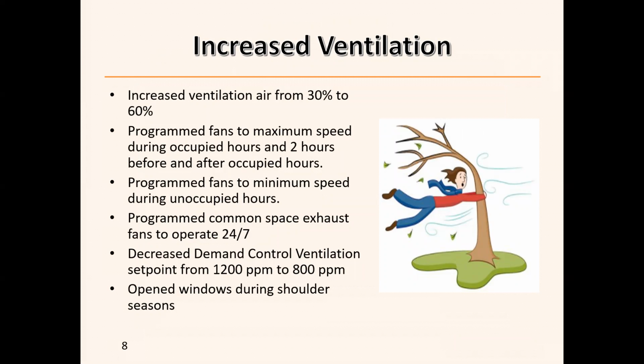Next, we programmed fans to run at a maximum speed during occupied hours and 2 hours before and after occupied hours so as to purge the spaces. Then we programmed the air handler fans to operate at minimum speed the remainder of the hours, so during unoccupied hours, so that there is continual air movement and air changes.